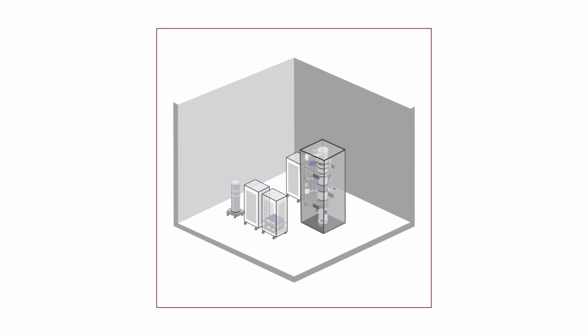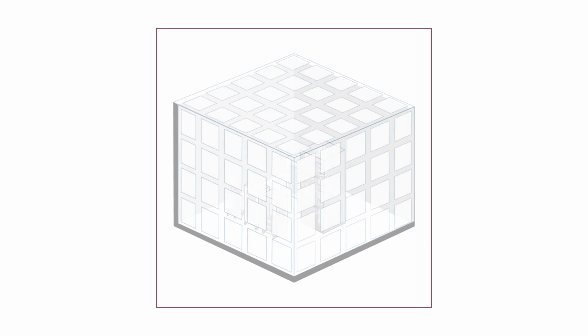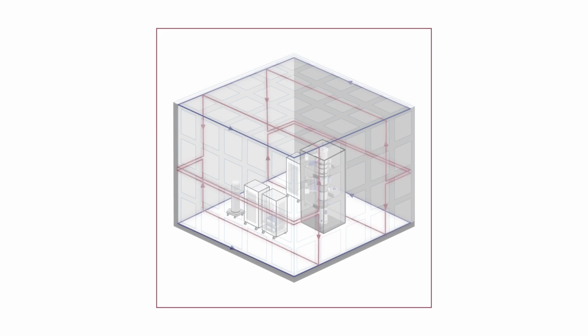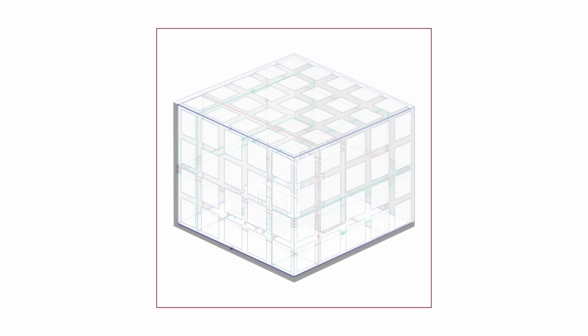Another approach that we see with customers with both DC and AC field issues for high-resolution TEM labs is the integration of a dual cancellation system with eddy current passive shielding for AC fields. Many customers like the permanency that AC eddy current shielding provides, but remember the DC field sensitivity of these instruments is extremely high, and it doesn't take much for the specification to be breached. So we often see customers use aluminum AC shielding to mitigate the AC component of the magnetic fields, and then a dual cancellation system to mitigate the DC component, providing both DC and AC shielding for the TEM. I hope this video was helpful for you to understand both the challenges and strategies for mitigating both DC and AC magnetic fields.